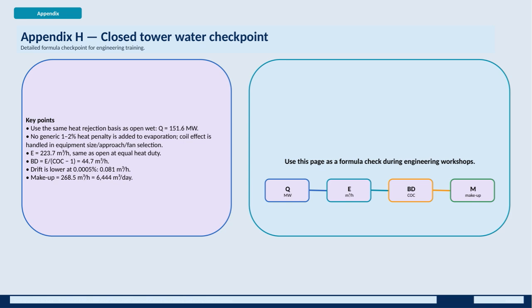First, we use the same heat rejection basis as the open wet system, which is 151.6 megawatts. Unlike some assumptions, there's no generic 1 to 2% heat penalty added for evaporation here, because the effect of the coil is accounted for in the equipment's sizing, approach temperature, and fan selection. When it comes to evaporation, the rate, represented as E, is 223.7 cubic meters per hour, identical to the open system at the same heat duty. The blowdown rate, calculated as E divided by the cycles of concentration minus 1, is 44.7 cubic meters per hour.